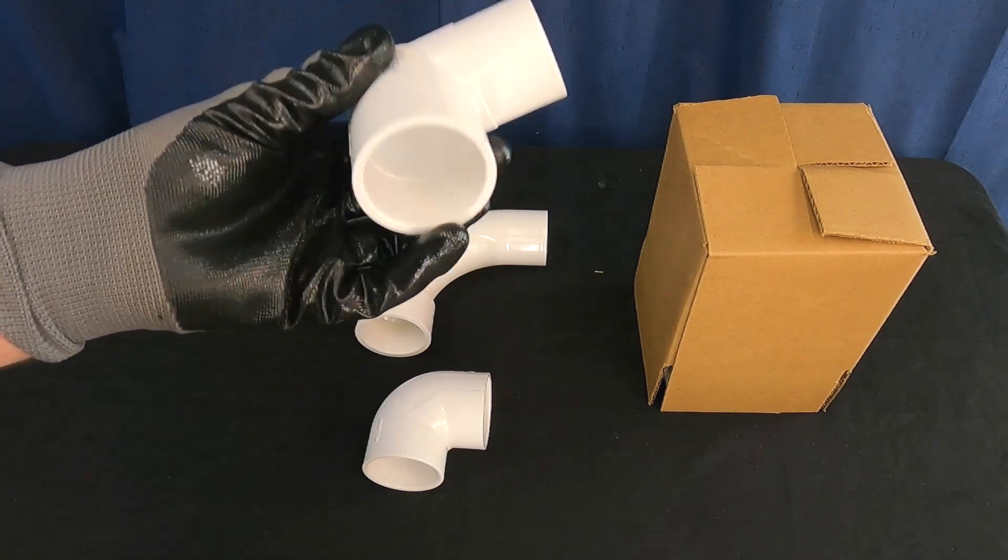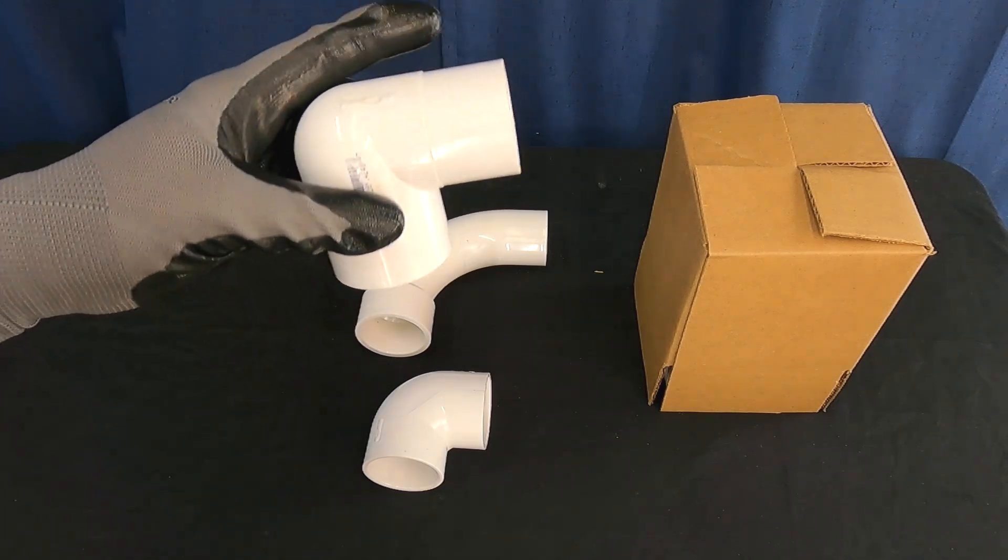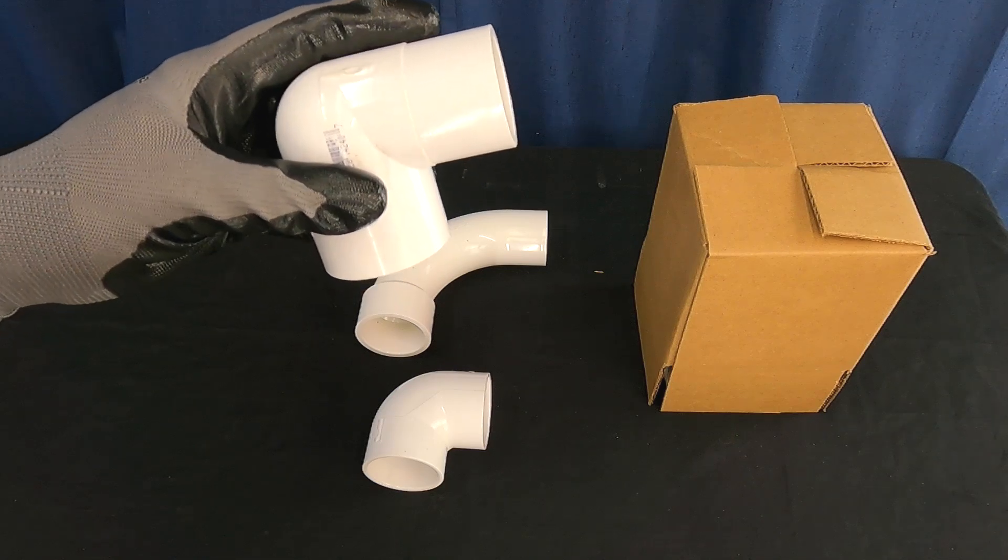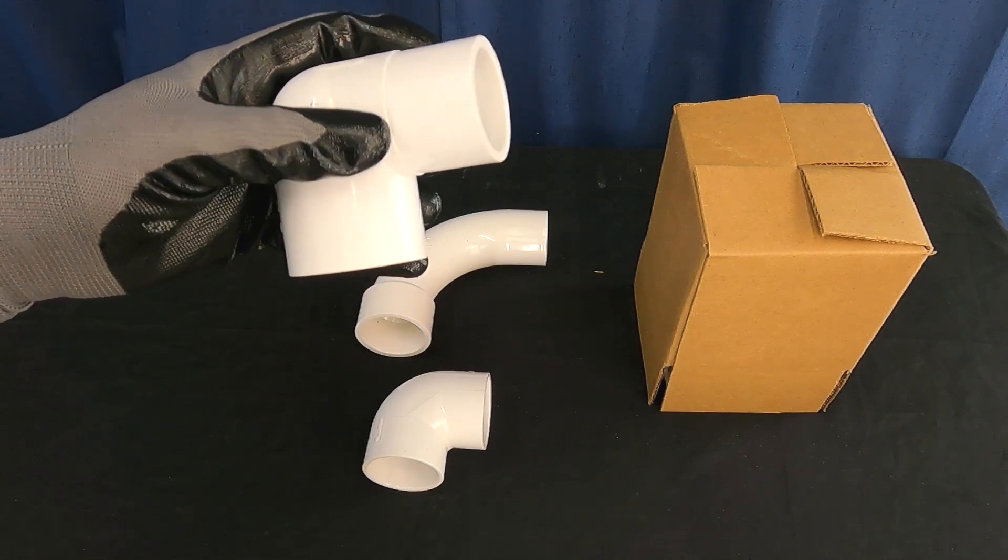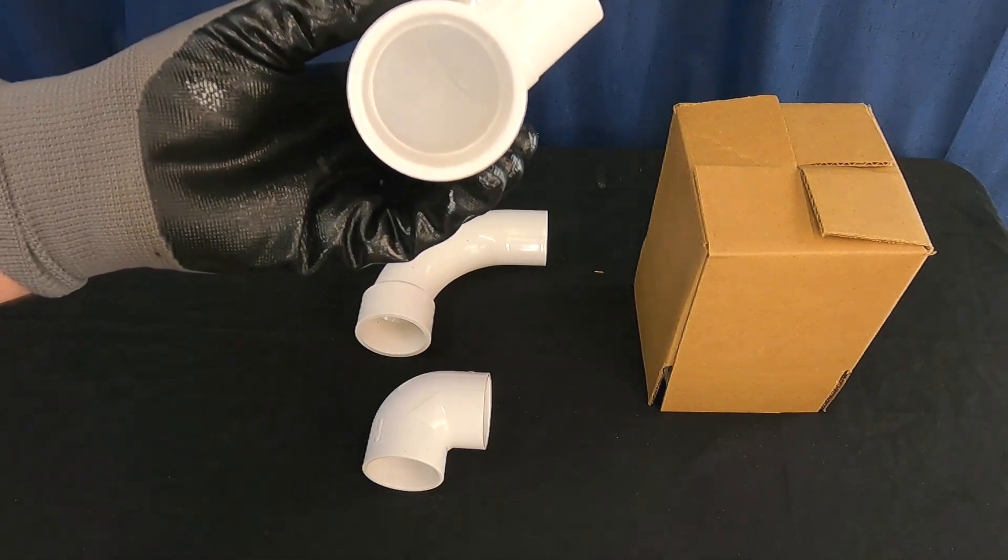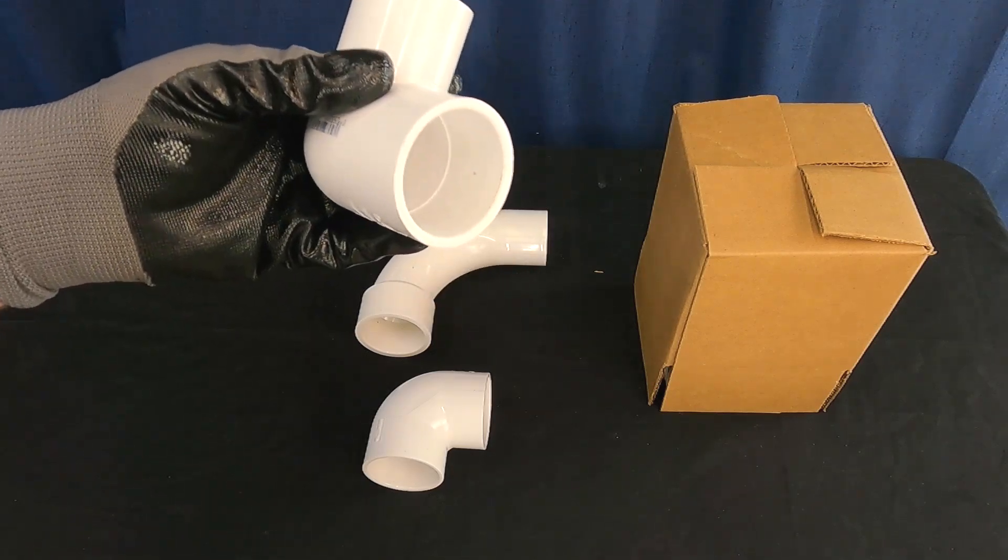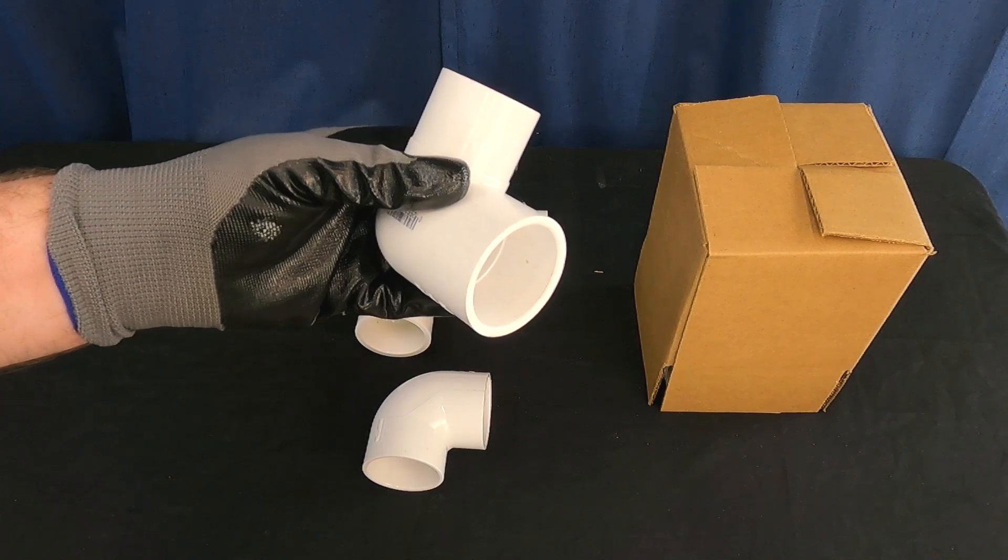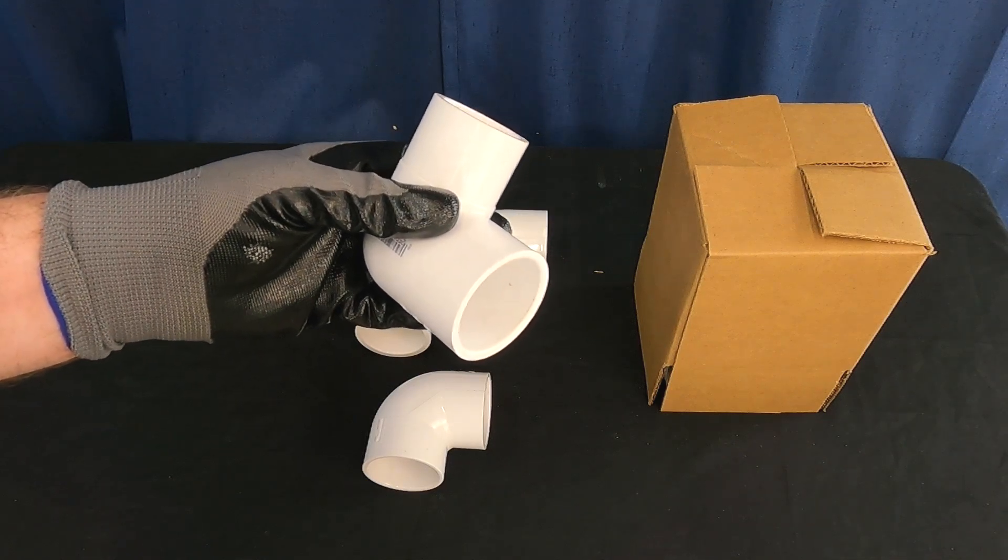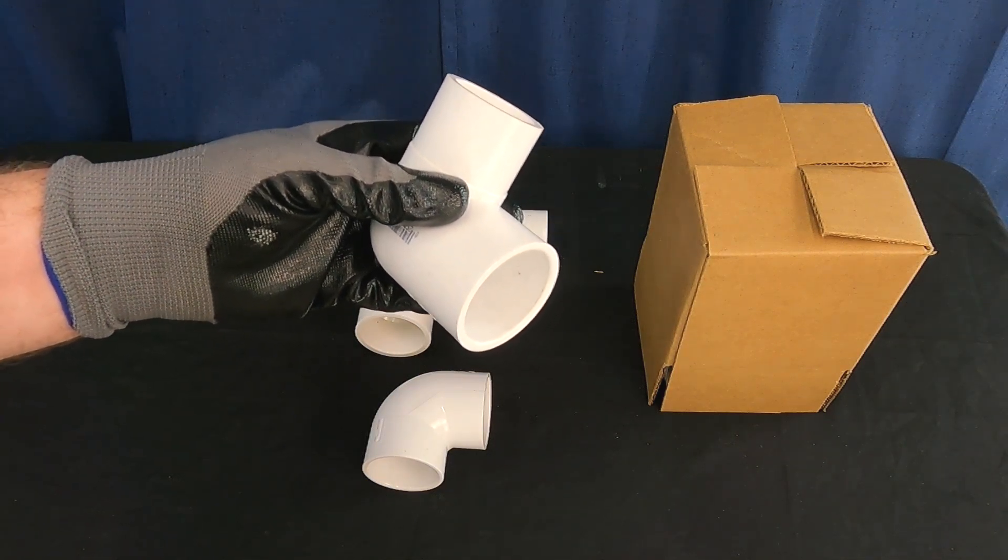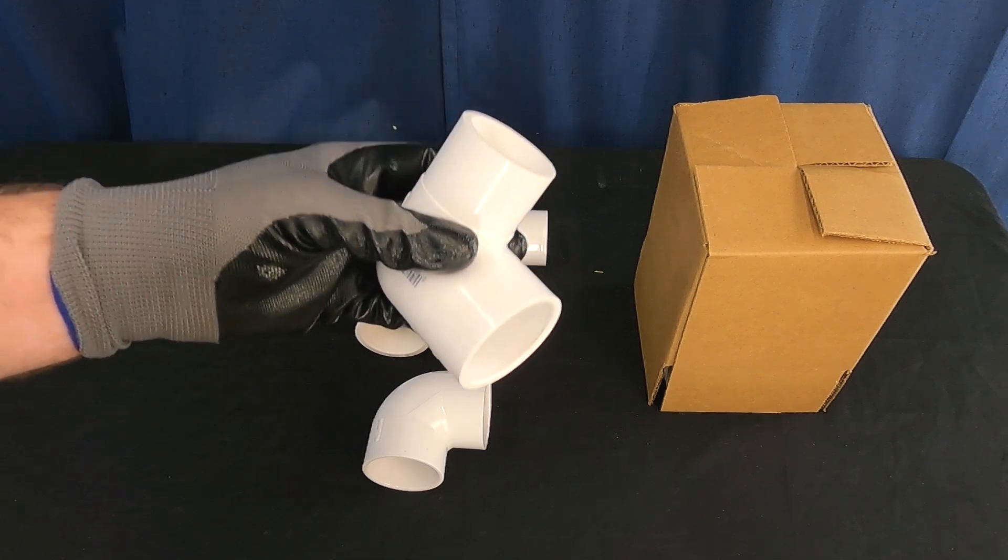It's a slip port on one side which is fine, but we have a spigot port on the other so that glues into another fitting. It's really like the hydraulic equivalent of a brick wall because it doesn't help the water to transition the turn at all. As a result there's an unusually high amount of energy loss, friction created in this fitting.